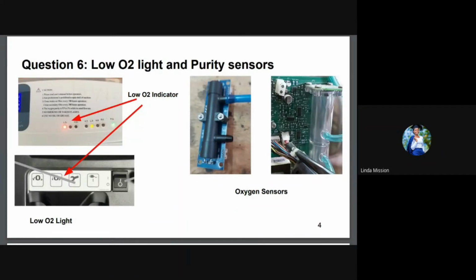If after fixing the disconnections the LED still illuminates, then the sensor can be faulty. You should remove it and replace it with a working sensor. If the LED turns off with the new sensor in place, then the problem was with the sensor, so you have to replace it. So in the graphics, those are the 2 oxygen sensors that are used in concentrators, and the other image is just showing the low oxygen purity indicator on different concentrator models. Thank you, Maui.